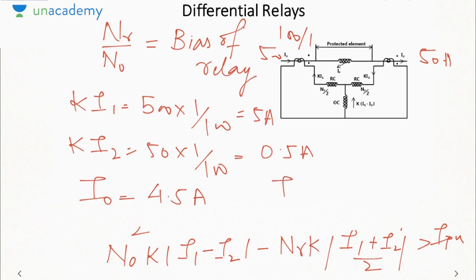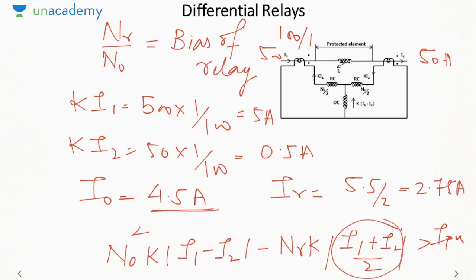And what will be the restraining current? It is K into I1 plus I2 by 2, that is 5.5 by 2. So it is 2.75 ampere. Now if you see, the difference between these two currents is very high. If it is greater than the pickup value, then the relay will operate, and otherwise the relay will not operate. So that is the basic condition for the percentage differential relay.